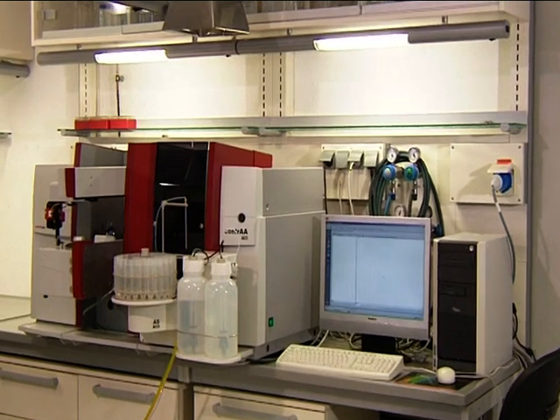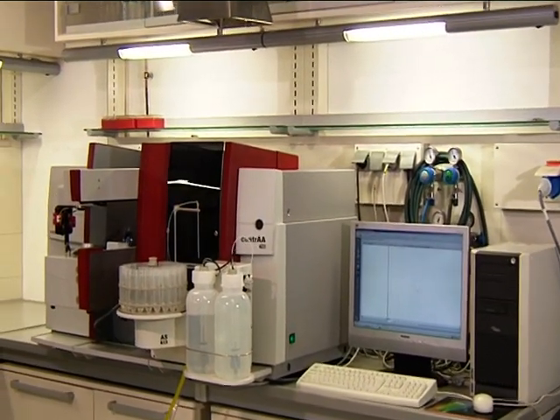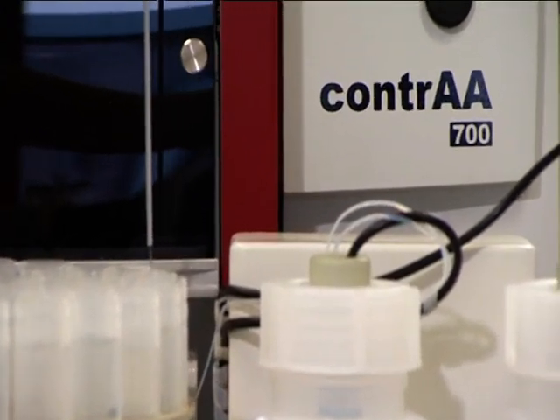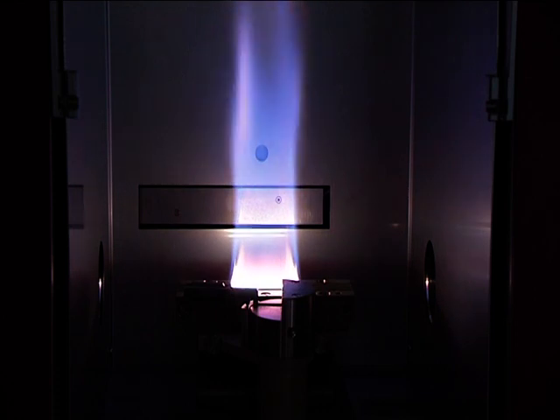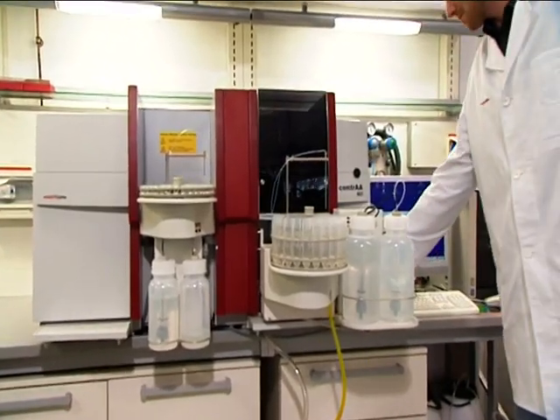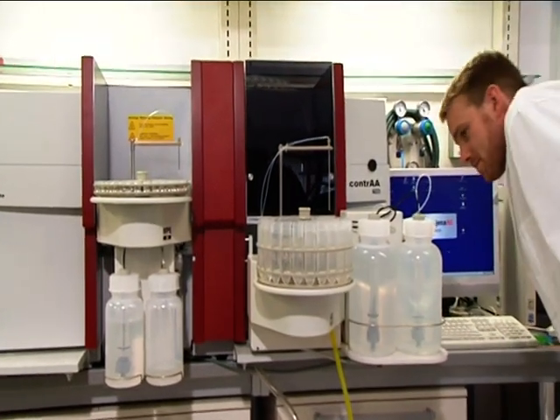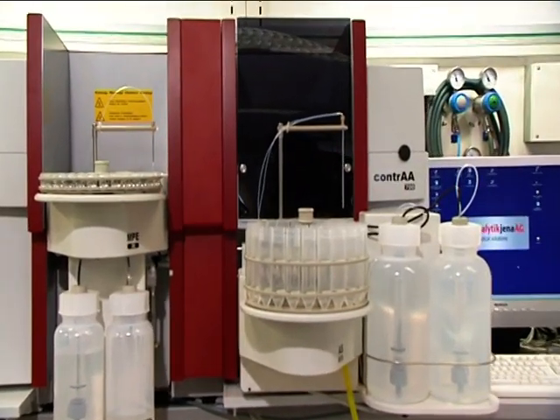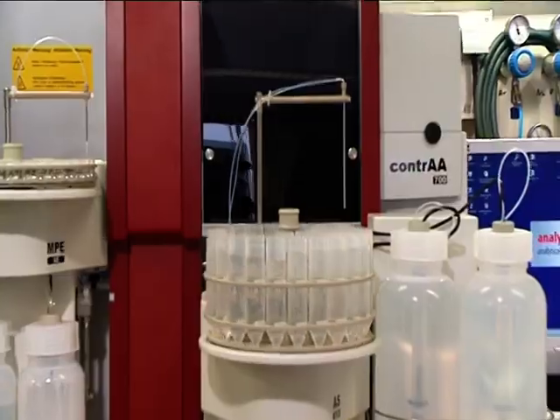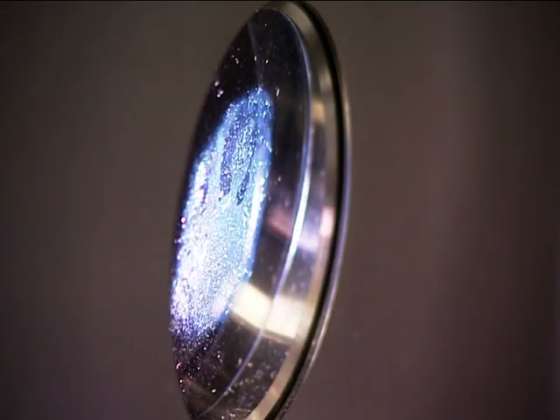High-resolution continuum source AAS, an innovative technique, closes the gap between traditional AAS and the ICP OES. A single source of radiation covers the whole analytically usable spectral range, and with that replaces all hollow cathode lamps of the classical AAS technique.